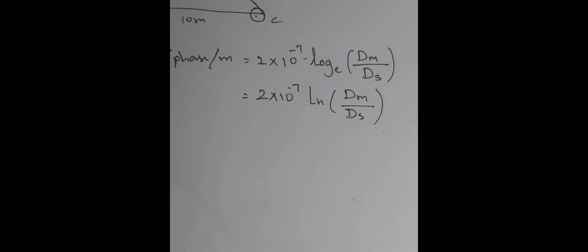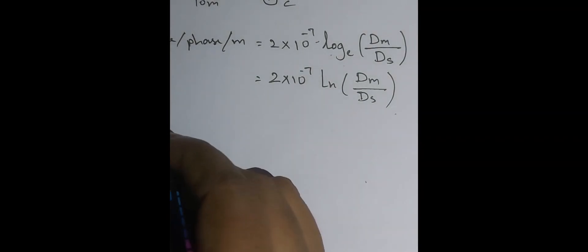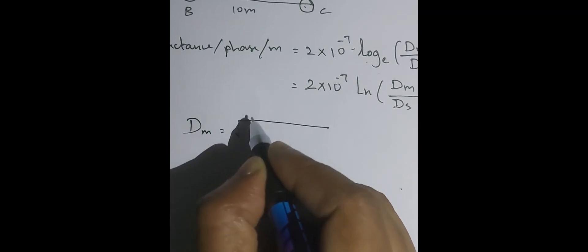This is a very useful shortcut formula: 2 × 10⁻⁷ × ln(dm / ds). Now we have to find dm, which is the mutual geometrical mean distance. For geometrical mean distance, you take the product of the distances and raise it to the power of 1 divided by the number of distances. Here we have only 3 conductors — A, B, C — each constituting one phase. The distances are: A–B is 4 meter, B–C is 10 meter, A–C is 6 meter.